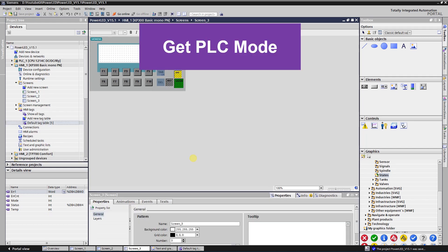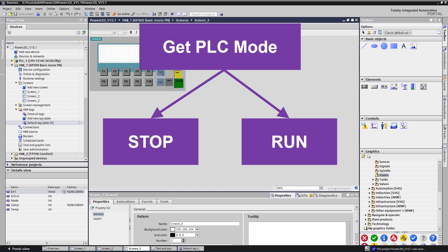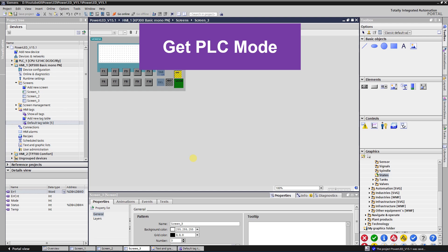PLC mode can be determined by the help of the function called Get PLC Mode. By firing this function it evaluates the current state of the PLC that has connection with your panel. There are two modes that can be monitored by this function: Run, which means that the PLC program is being executed, and Stop, which means that the PLC program has been interrupted. Be advised that this function works only with PLC S7-1200 and S7-1500 series.